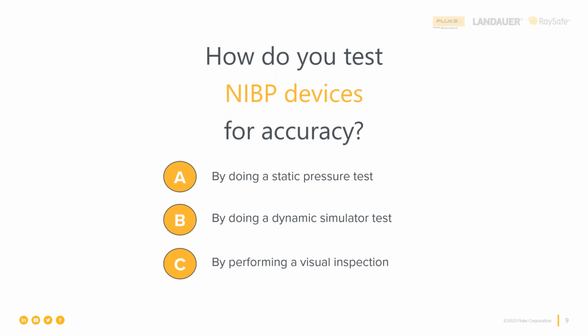I'm going to show you and talk to you about why the only way to assess accuracy in NIBP devices is by doing not just a static pressure test at one pressure level, but at several pressure levels. And most manufacturers that provide this, it's usually in their service manual testing procedure, will have more than one pressure level that you'll do the static pressure comparison. That's the only way, because in the dynamic simulation of blood pressure, there are too many variables that you cannot control all happening at the same time. In order to assess accuracy, it's got to be a single measurement, because you've got to have your stack up of uncertainties of confidence that your measurement was indeed accurate.